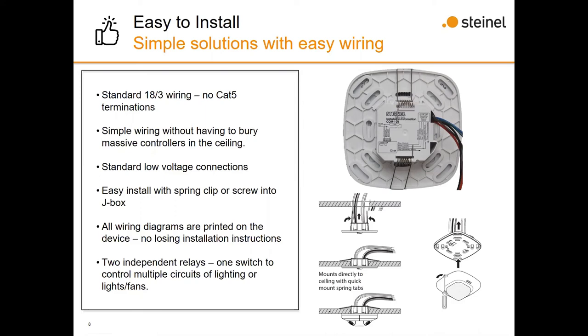You also have the capability within our sensors - if you're using, for example, a hallway sensor in the corridor, an ultrasonic in your restroom, and a passive infrared in an office, and you get them installed in the wrong places, you can pop the sensor head off of one and install it on the other. You can also, if you decide to go dual tech and find there's a lot of interference in the space and want to switch to passive infrared, very easily pop the head off and switch it with a passive infrared sensor head.